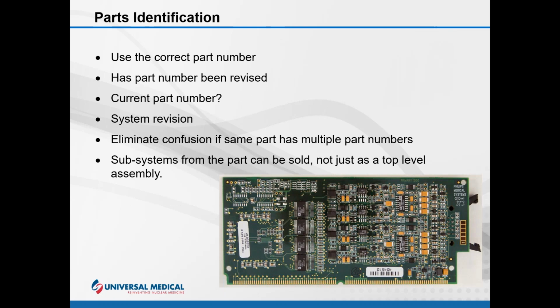And from there, let's move into parts identification. If a part number isn't available or you're not sure of the correct number, your preferred vendor will need a system type, description of part, or location of part on the system to try and provide a proper part ID. Most parts will have some type of identifying number or description located on them. And as you can see from the slide, the PCB or printed circuit board has a couple of labels on it, and it can be a little confusing on occasion what the actual part number is.